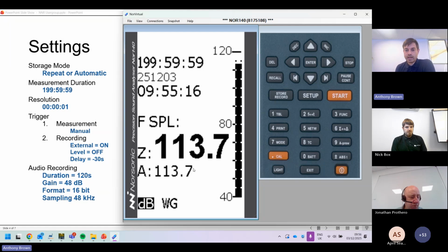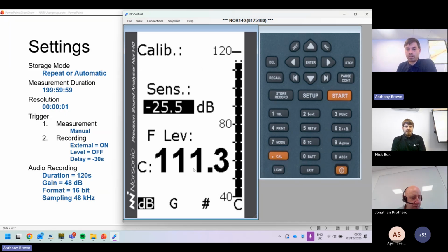So to change the calibration, and if you haven't got the calibrator, then don't follow along with this, just skip this part. But if you have the calibrator, press the cal button on the keypad. So this big orange button, cal, just press this and you'll get this screen here. And all I want you to do, there's two buttons at the top, dec or inc. Because I'm at 113, I'm going to need to press the dec key. If you're above 114, you'll probably need to press the inc key.